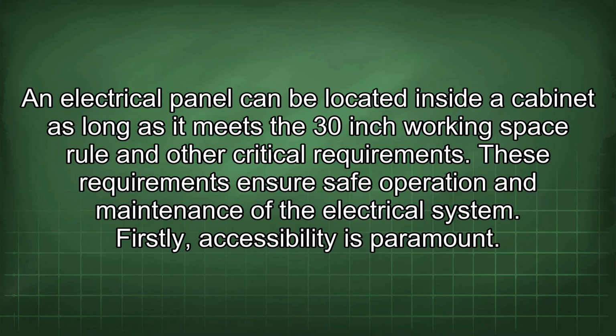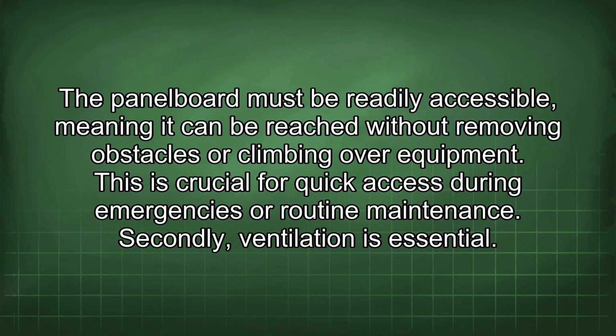An electrical panel can be located inside a cabinet as long as it meets the 30-inch working space rule and other critical requirements. These requirements ensure safe operation and maintenance of the electrical system. Firstly, accessibility is paramount. The panel board must be readily accessible, meaning it can be reached without removing obstacles or climbing over equipment. This is crucial for quick access during emergencies or routine maintenance.